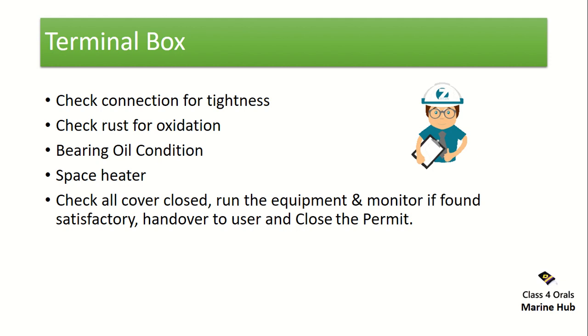Check the terminal box — verify the tightness of connections, check for oxidation, rust, or any foreign particles, and check the bearing oil condition on the alternator — it should be clear with no foreign traces. The space heater should be working — press the button and check whether the heating of the cabinet and terminal box is functioning. Check that all covers are closed and all screws and fittings are tight.